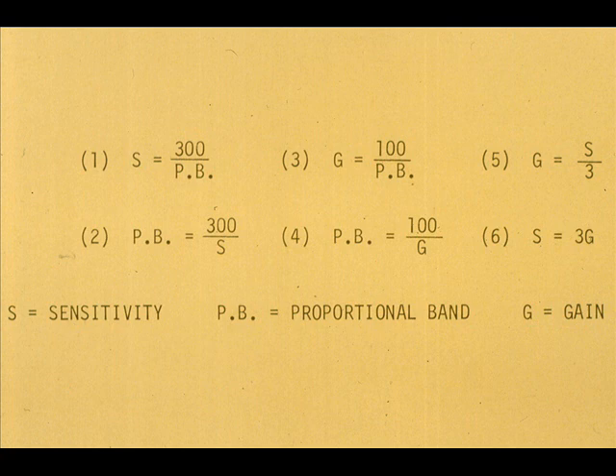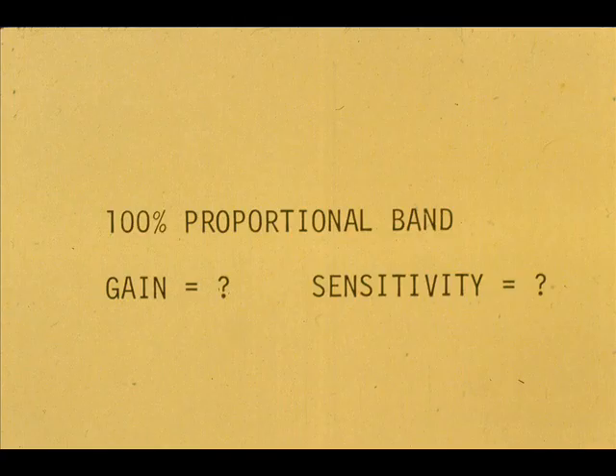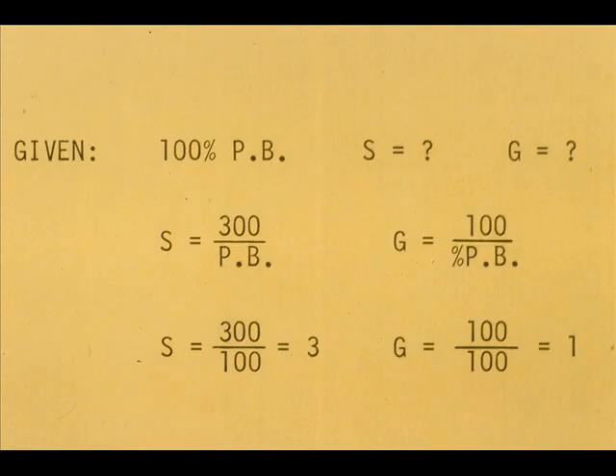Sensitivity is not widely used. These six formulas will make any conversions between the three terms. For example, a controller has 100% proportional band. What is the equivalent gain and sensitivity? For 100% proportional band, the equivalent sensitivity is 3 and the equivalent gain is 1.